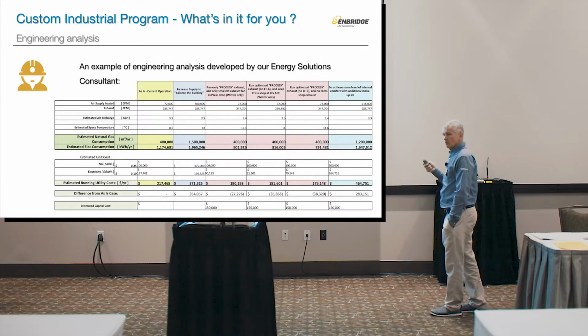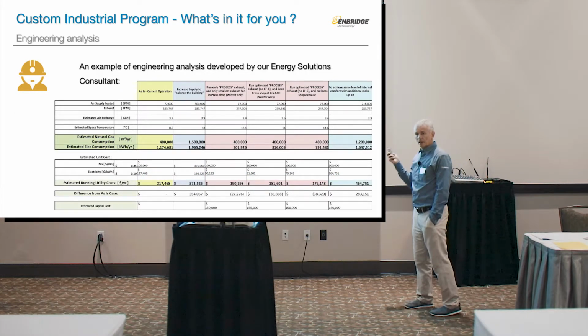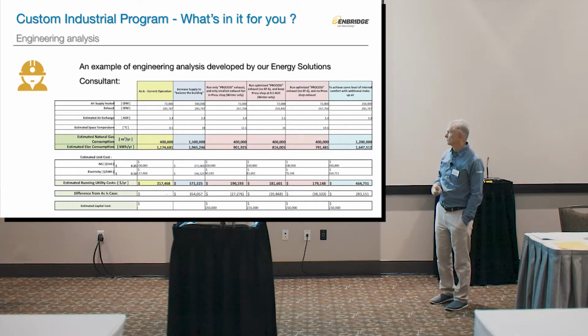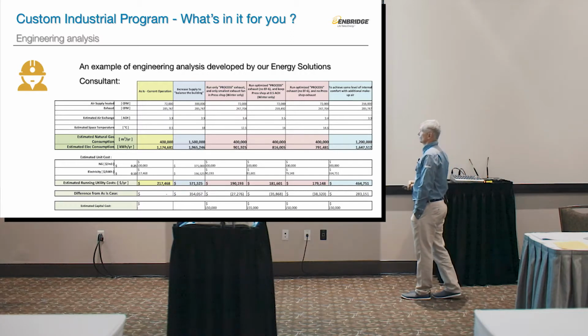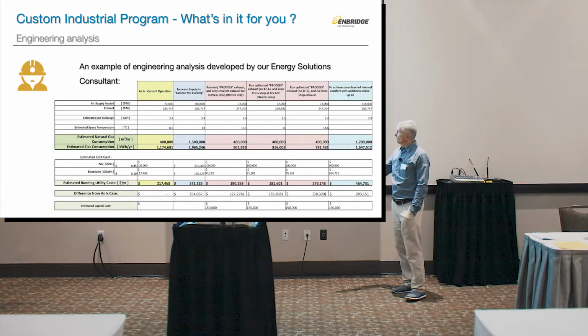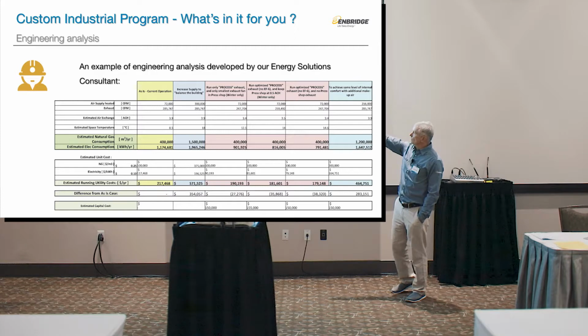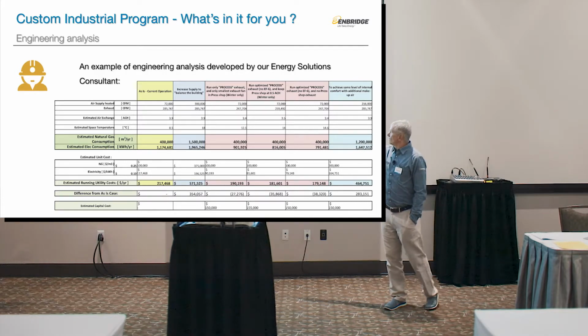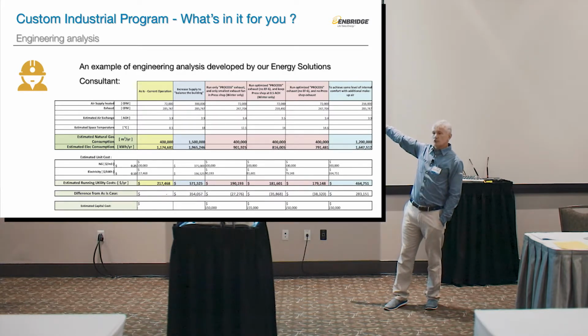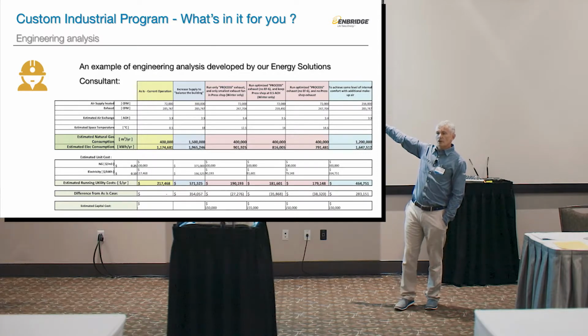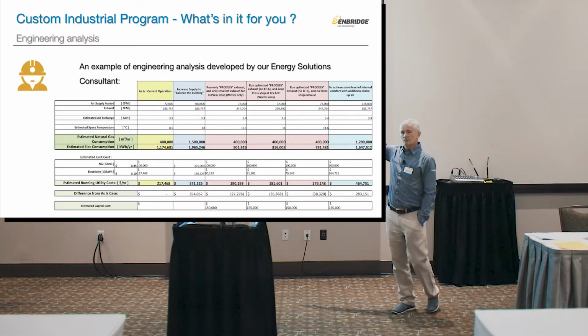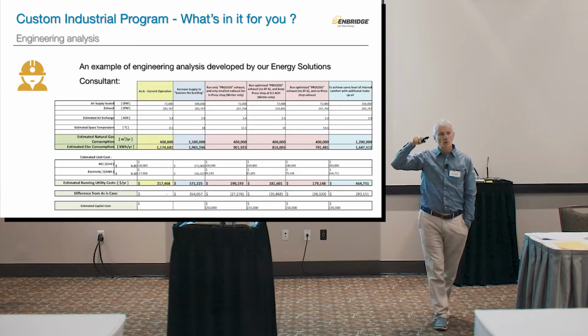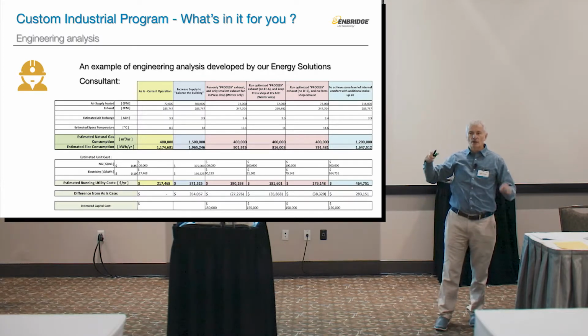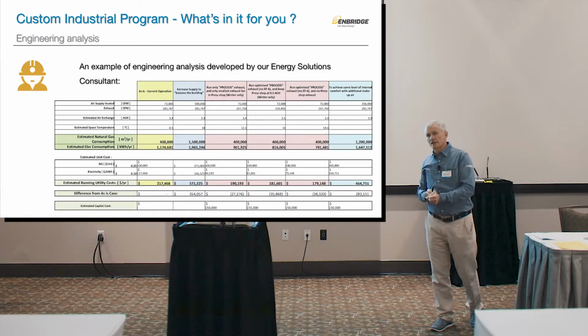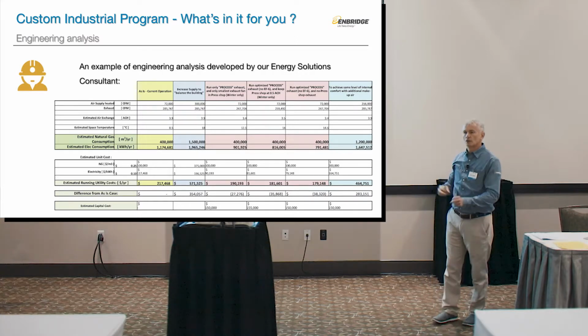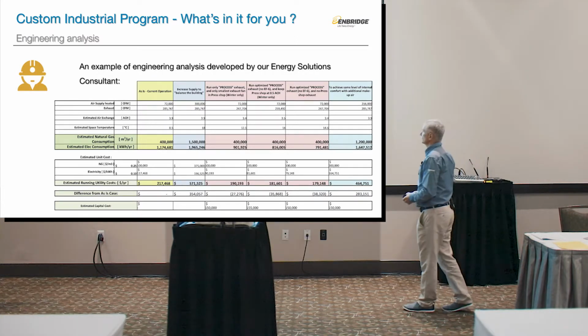This is an example of one of the analyses done by our energy solutions consultant for a customer, to give you an idea of the complexity. As-is current operation is in the first column. What the customer wanted to do was increase the supply of makeup air to balance the building. This is a big thing I hear a lot: my building is negative, so I want to install more makeup air to balance it.